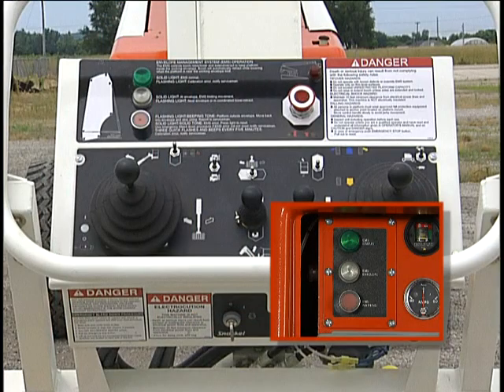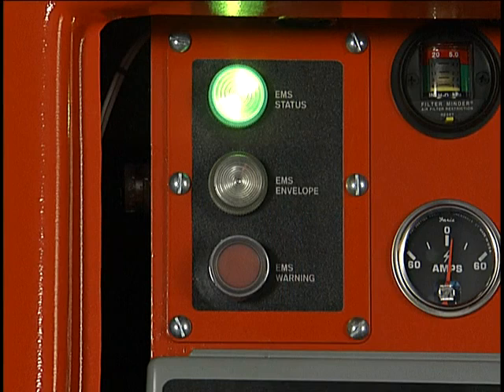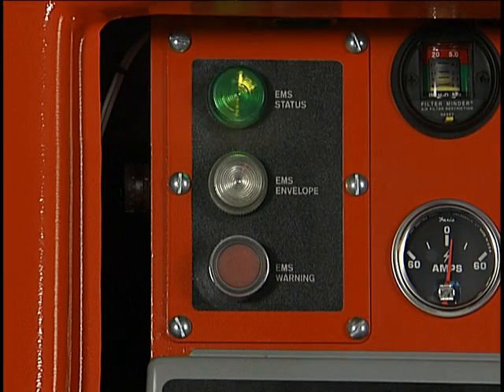There are identical EMS status and warning lights on the upper and lower control panels. A green status light indicates that the machine is on and ready for operation. If the green light is flashing, it indicates a calibration error, and the machine should not be operated until a qualified technician fixes the problem.